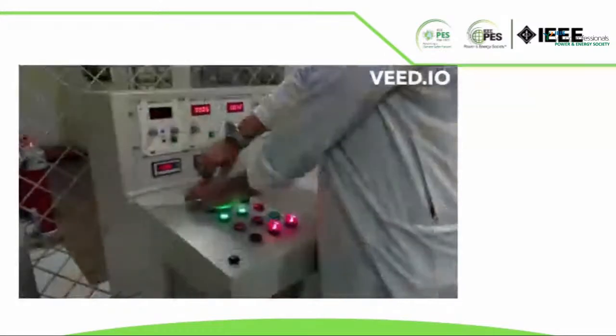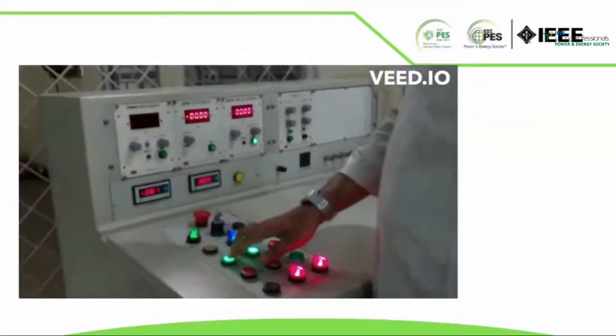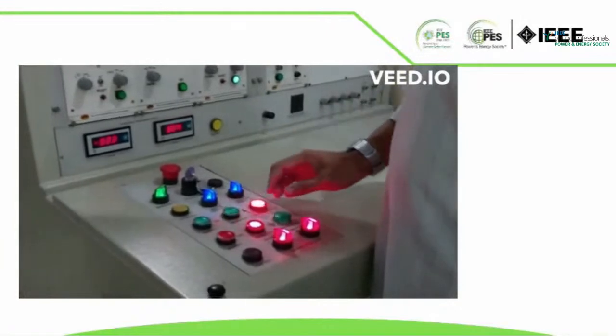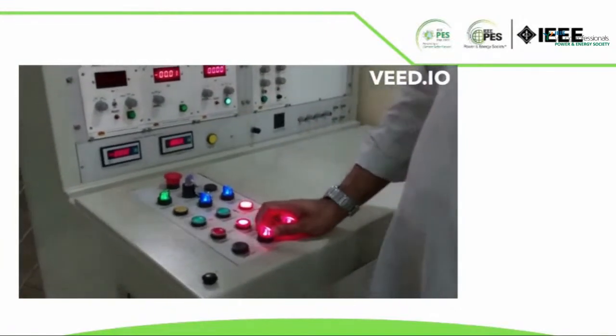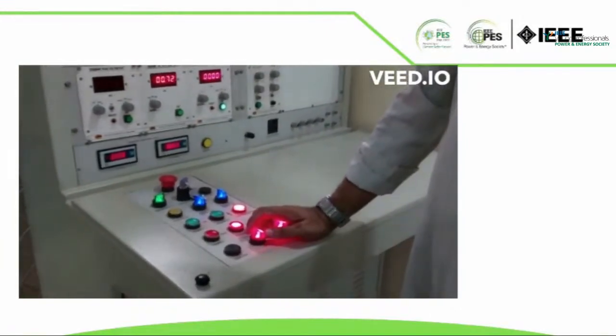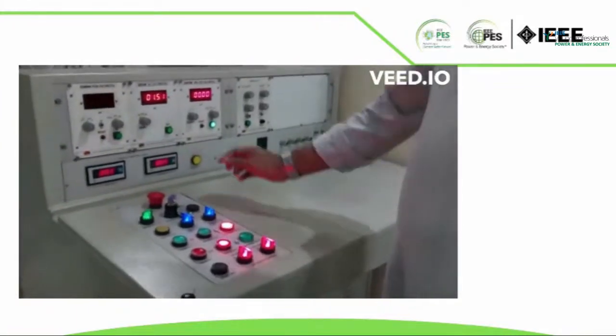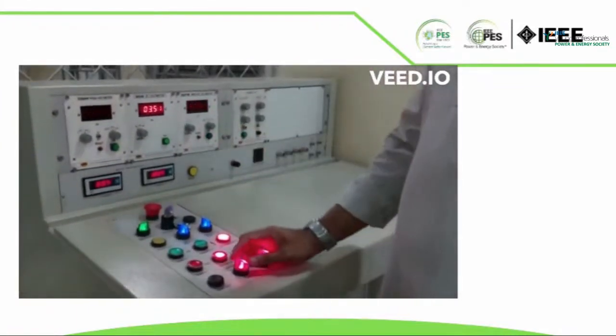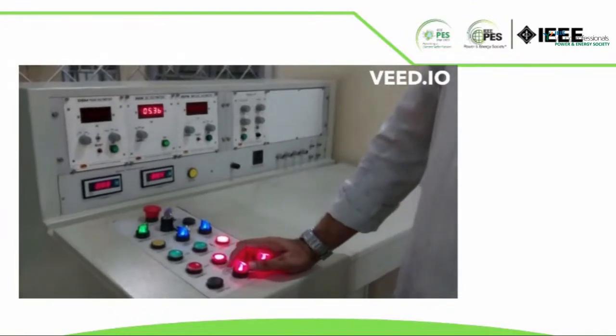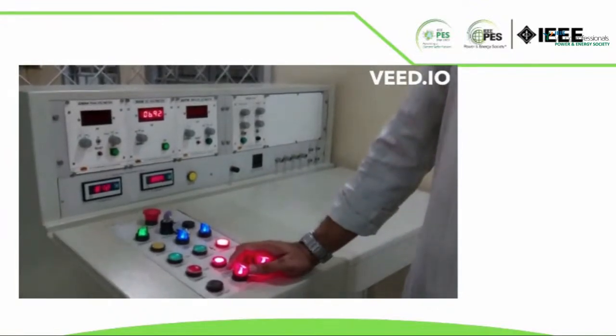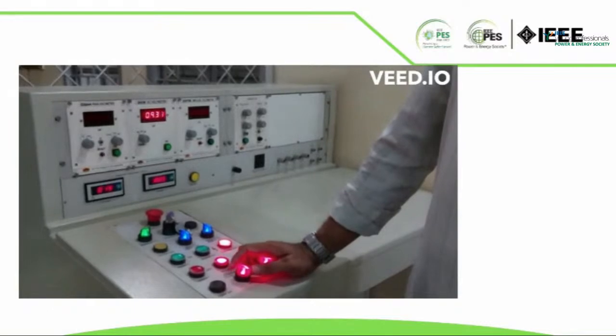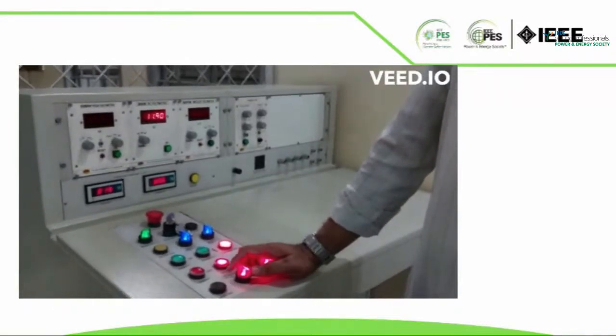Now we shall see a short video of high voltage DC testing using a vertical sphere gap arrangement. This is the high voltage testing transformer of 5 kVA, 230 V/100 kV output. This AC voltage is rectified using the two diodes here and then given to an RC circuit which gives a high voltage DC output across the vertical sphere gap.